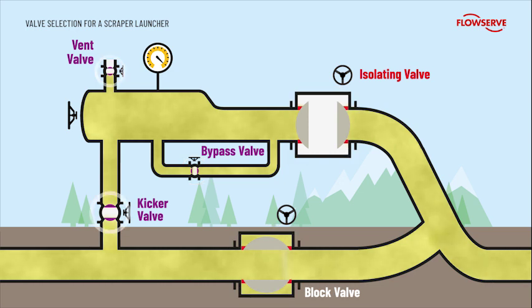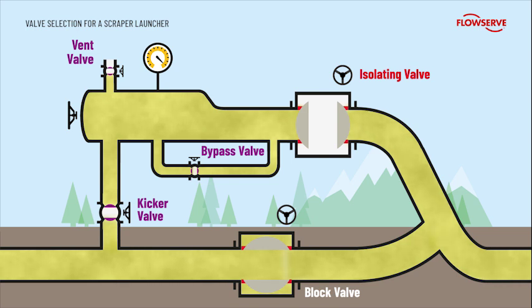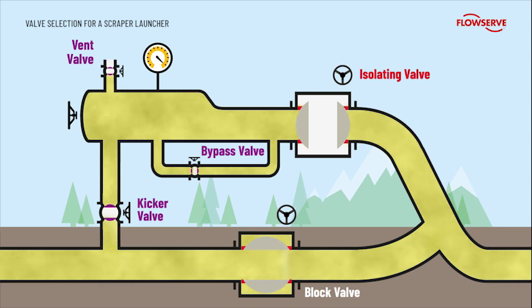You will note that some valves have to open against full differential pressure or allow throttling of the flow to occur, whilst providing a bubble-tight seal. In these harsh applications, a plug valve is the preferred choice.